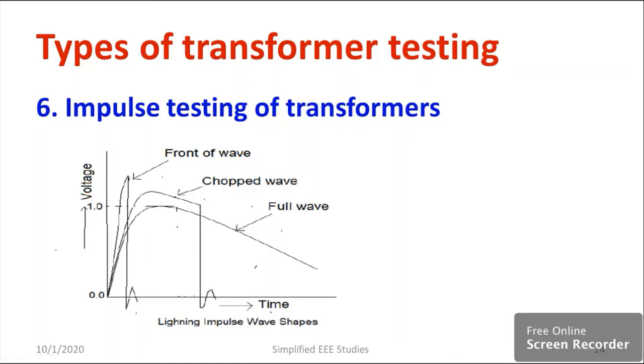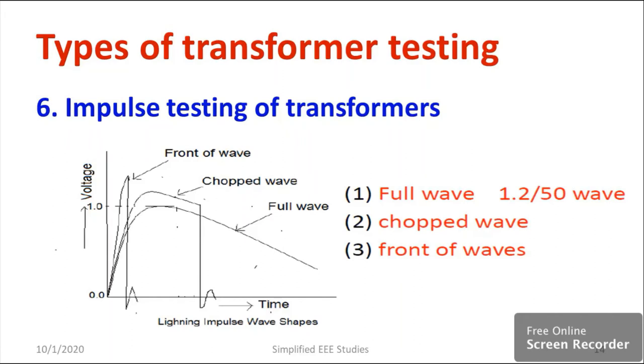These waveforms are generated for testing purposes using an impulse generator. They are directly applied over the transformer insulation and you observe any changes — what about the wave shape, whether you are getting pure waveforms, or if there is any sudden collapse of voltage. The first type is the full wave, the second is the chopped waveform, and the third is the front of wave. If you find any sudden voltage drop or dip, you will know there is a problem in the transformer insulation that cannot withstand lightning and thunder.